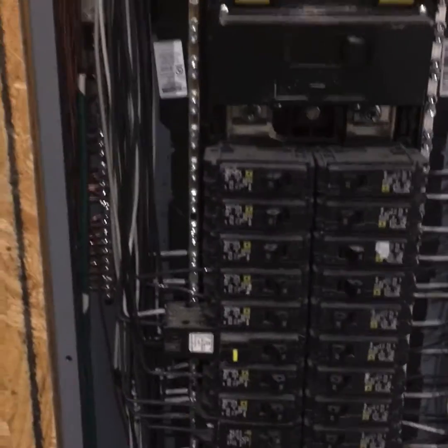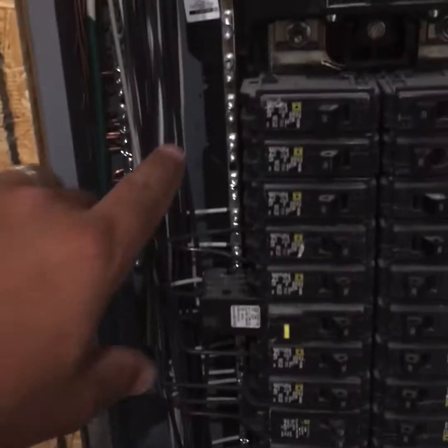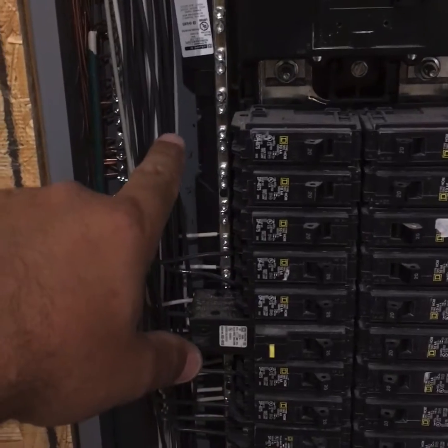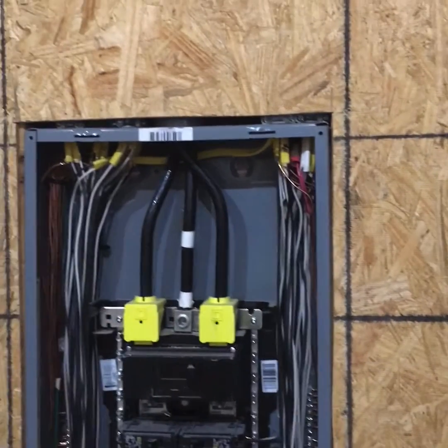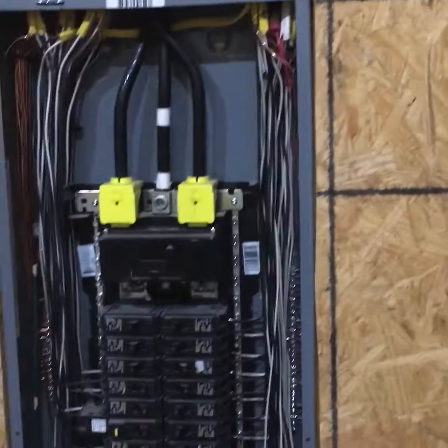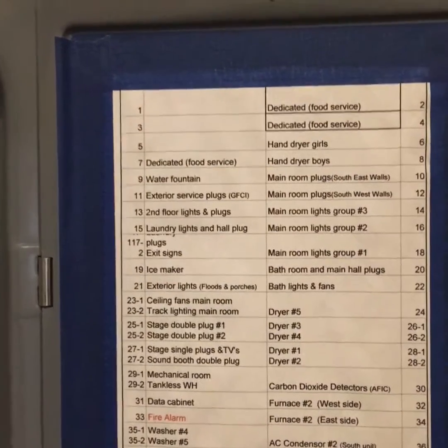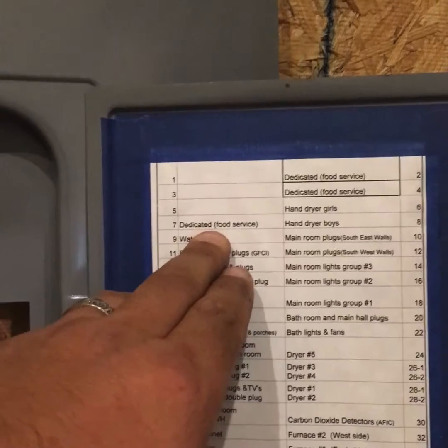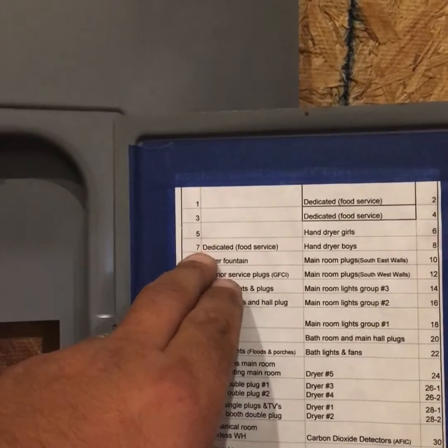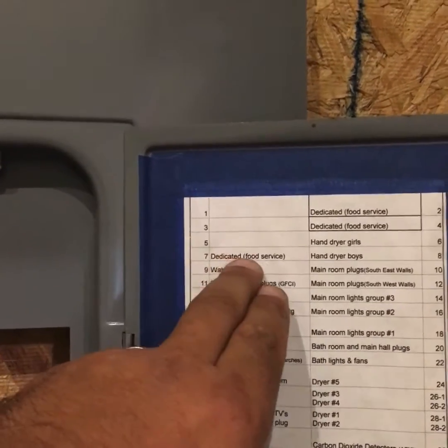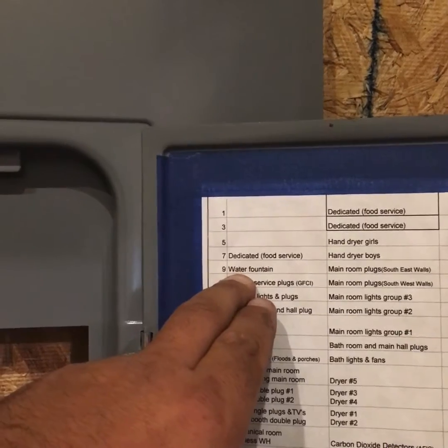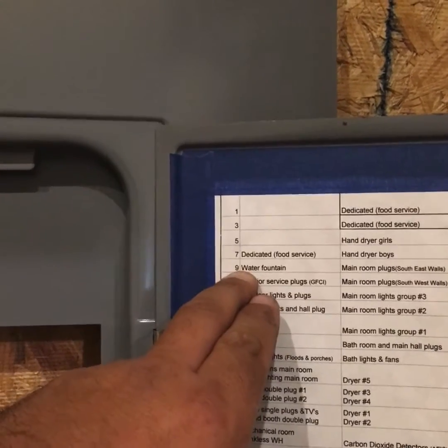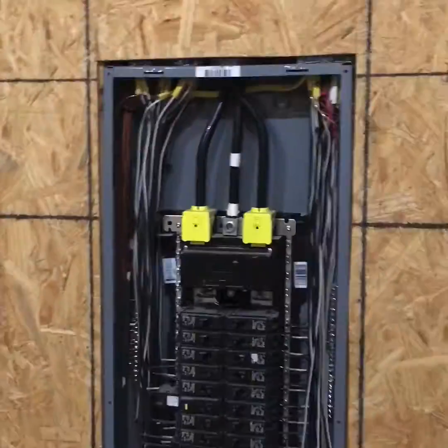So what I do that most people don't is, with a Sharpie, before I start landing wires, I write on here 1, 3, 5. I lay everything out. I don't even have breakers in the panel yet. And then as I am pulling my wire in, I will write on that wire the circuit number. And that is determined from a blueprint that I have already sketched out, this whole building, in advance. I have already printed this off in advance. I have this stapled to the wall or to my prints. And as I am pulling the dedicated food service, this is probably for a warmer or something, I write on that wire number 7. I am not writing dedicated food service. When I pull the number 9 circuit to the water fountain, I am not writing by hand water fountain. I'm just writing a number 9. That allows me to tie this panel off so much faster.